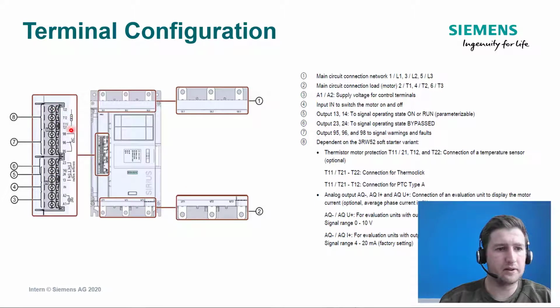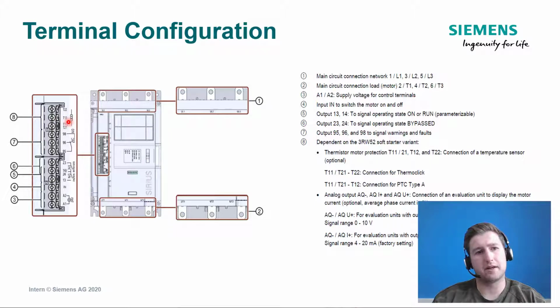T22, T12, and T11 are there for thermistor sensors. You can either have a thermistor, or you can have a thermoclick. Or if you choose, rather than thermistors, dependent on whether you've selected thermistor or analog, you can have that as an analog output as well. So you can measure with an external device, whether that's an ammeter or a voltmeter. There's an option dependent on which part number you select. You can either have a thermistor on this terminal, thermoclick or PTC, or an analog output.